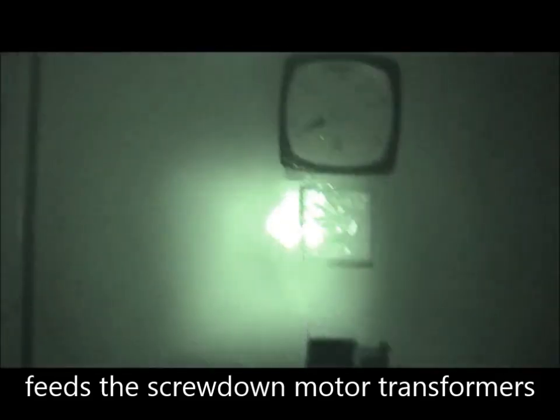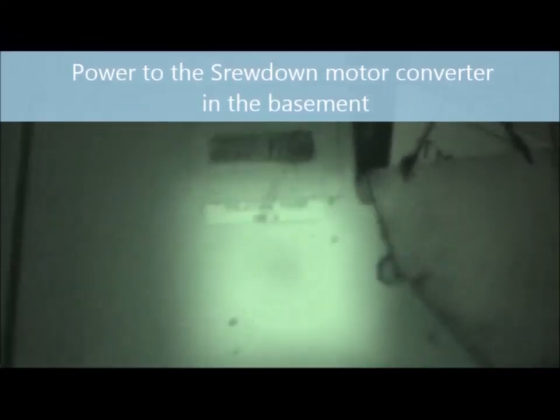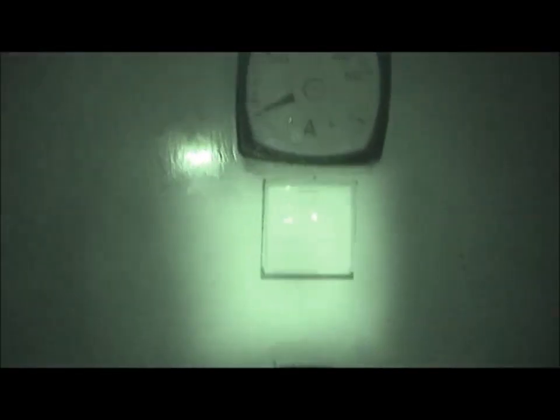Move through to the screw down board F, fed from the 250 MVA board, which is on the compound on the right. We've got to close these 5 breakers to put the AC supply onto the screws. Screws 2. Screws 3. Screws 4.